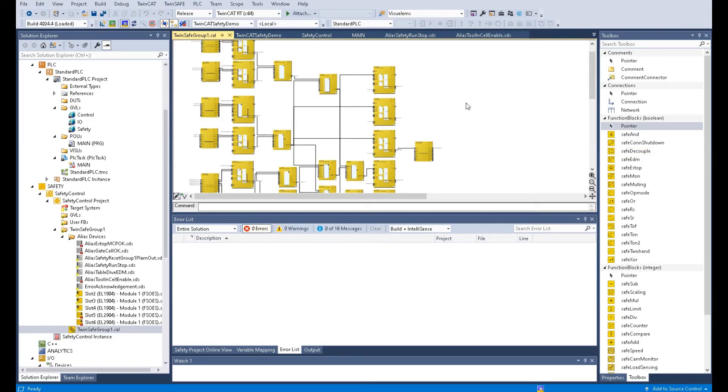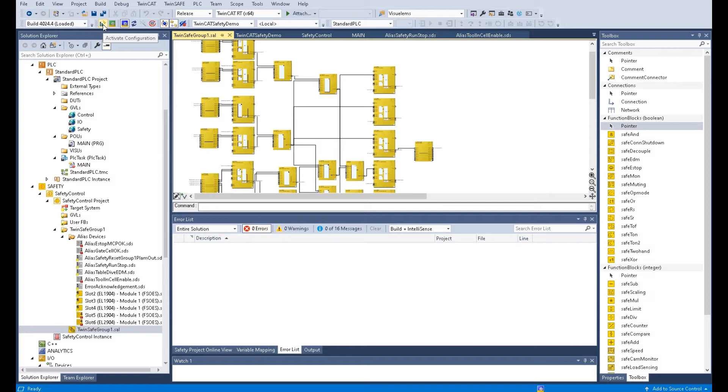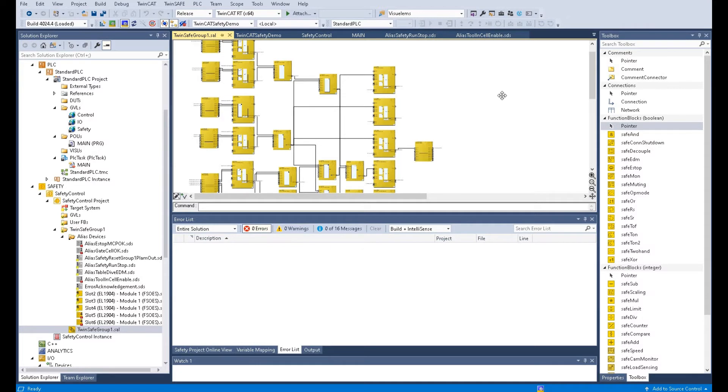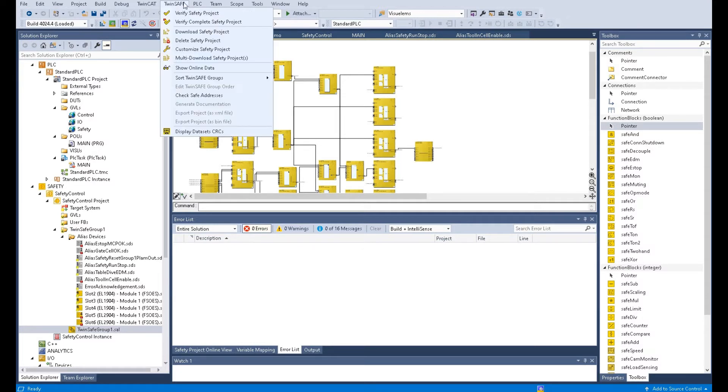Before we download the safety controller, make sure you already clicked activate configuration and downloaded all the PLC hardware already. Because after you download this activate configuration, basically TwinCAT will download all the hardware configuration to the entire controller.